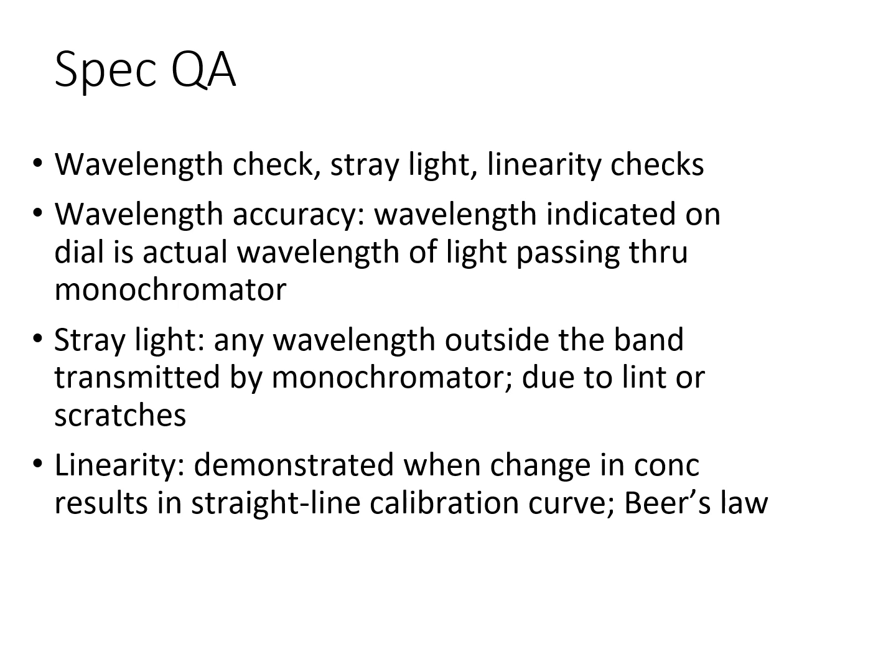Stray light is defined as the light outside the selected wavelength band that reaches the detector. Some causes of this could be a scratched optical surface or dust or lint has found its way into the instrument. It leads to baseline errors and nonlinear absorbance at high concentrations. Tests use cutoff filters or specific solutions that absorb light fully at a given wavelength.